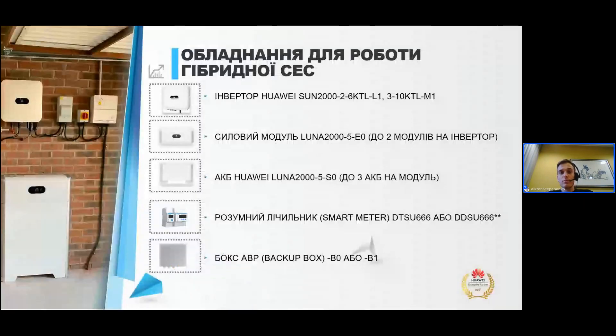Найперше потрібно згадати про обладнання, яке вам потрібно для гібридної станції. Це сам інвертор Huawei — L1 серії однофазний або M1 серії трифазний. Це силовий модуль як мінімум один, потужністю 5 кВт. Це акумуляторна батарея як мінімум одна, ємністю 5 кВт-годин. Обов'язково має бути розумний лічильник або смарт-мітер. І бокс АВР або бекап бокс — B0 однофазний та B1 для трифазних інверторів.